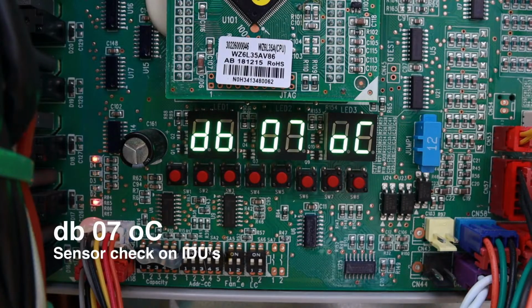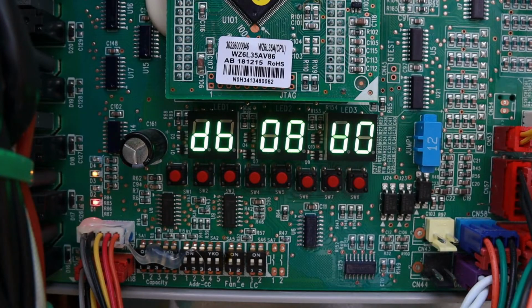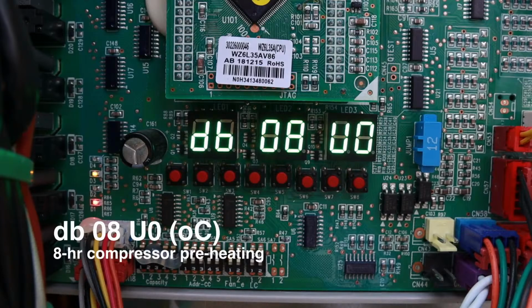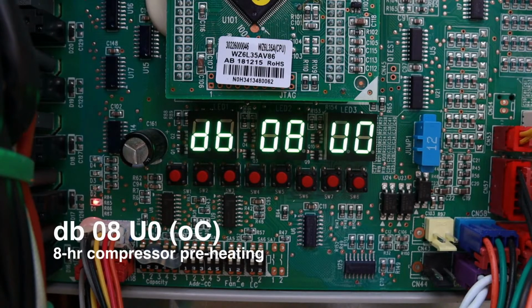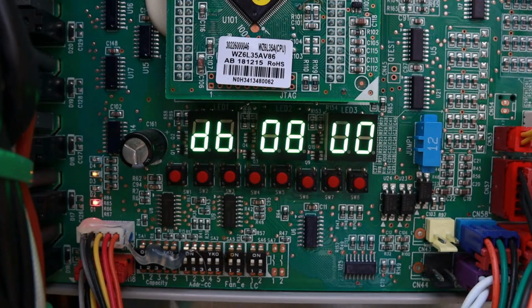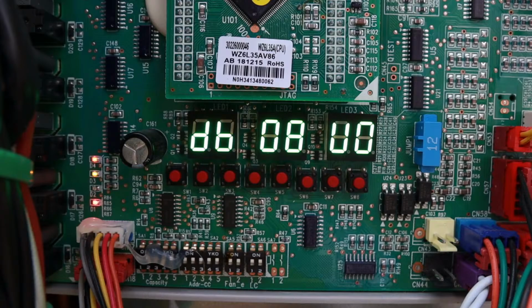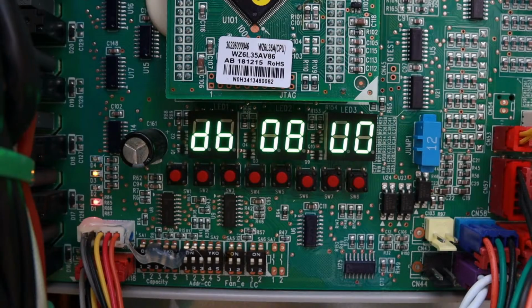Step 7 is an internal check for the sensors on the evaporators. Also give it about a minute or so. Then comes step 8, which is the 8-hour preheating cycle for the compressor. I always recommend to wait the 8 hours. Do not try to force it. Do not try to skip it. Just give it 8 hours for the system to do its job, which is to extract any oil that could have mixed, or actually any refrigerant that could have mixed with the oil. So guys, just wait 8 hours until the system does its thing, and then we're ready to go.